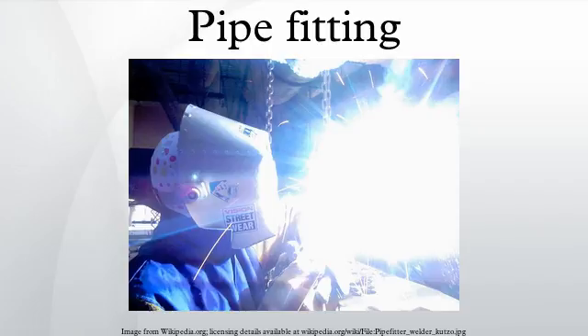In Canada, with respect to natural gas and propane, black iron pipe is commonly used to connect an appliance to the supply. It must however be marked and certain restrictions apply to which nominal pipe size can be put through walls and buildings. With propane in particular, BIP can be run from an exterior tank provided it is well protected from the weather, and an anode type of protection from corrosion is in place when the pipe is to be installed underground.